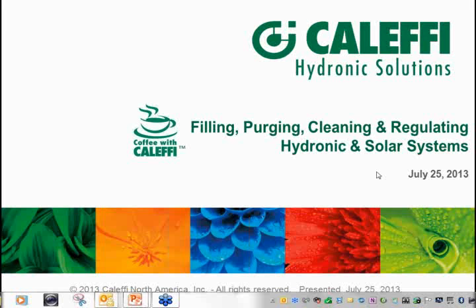What I did notice, we went down to the IGSHPA show a couple years ago, the International Ground Source Heat Pump Association. What I found down there, since those systems tend to be pretty big on the commercial side, is there's usually another contractor that comes in and takes that part of the job. So the installing contractor, the HVAC or mechanical contractor, would sub that out on a job and have somebody come in with the right equipment and the right chemicals to put in there and clean it, test the quality of the water, make sure everything's fine.